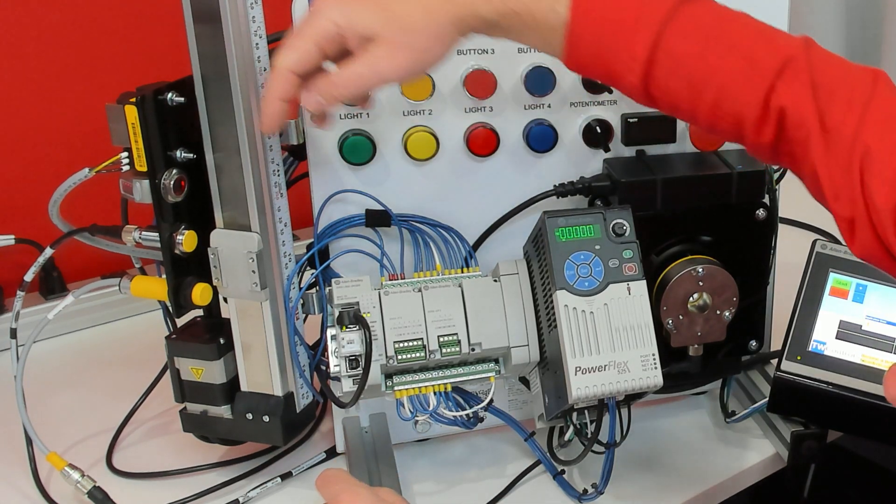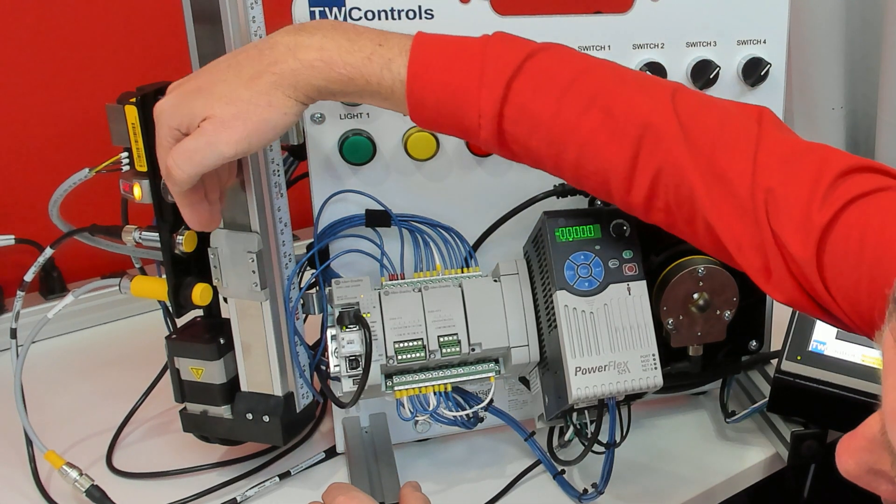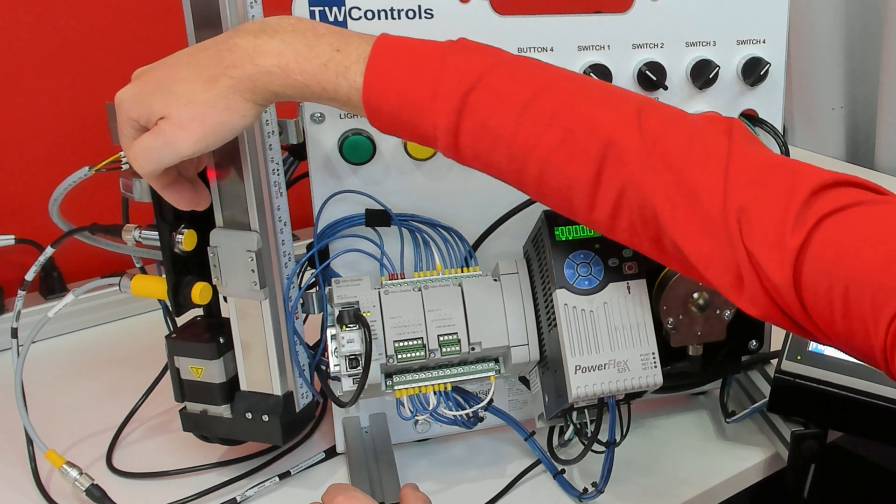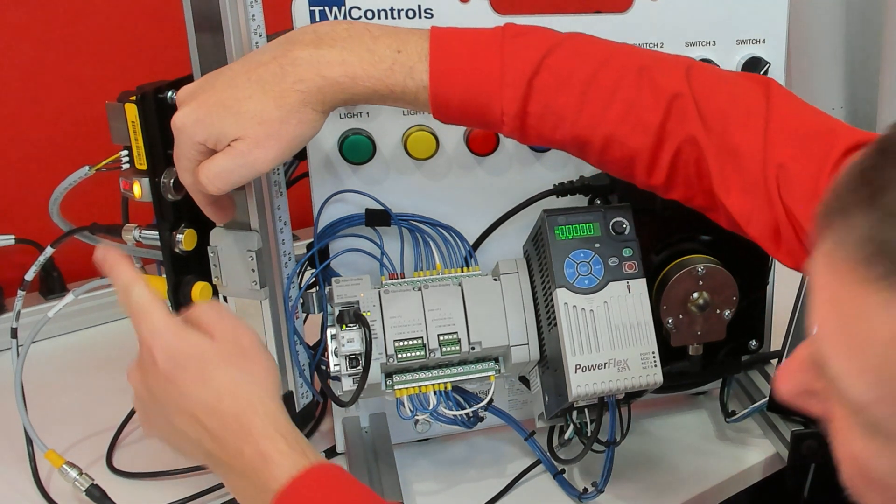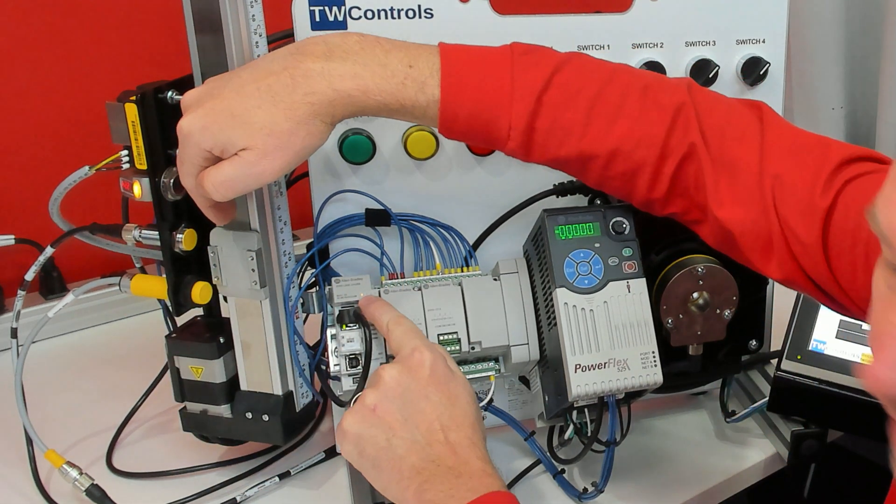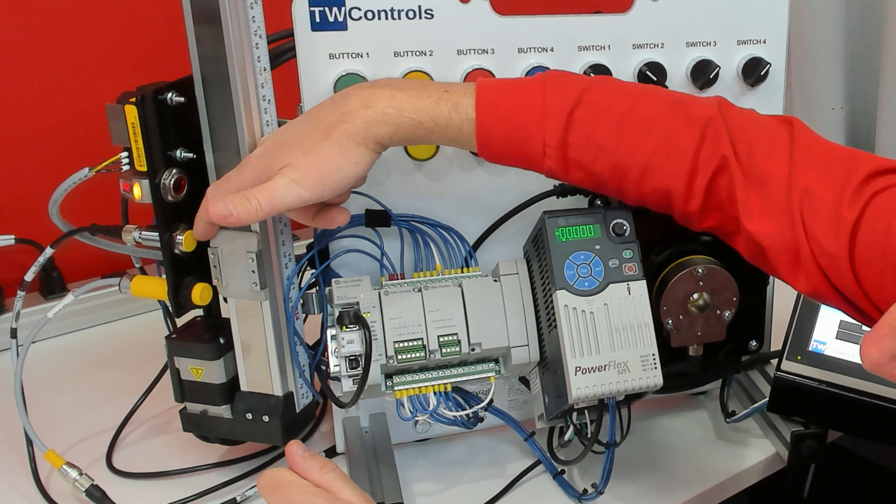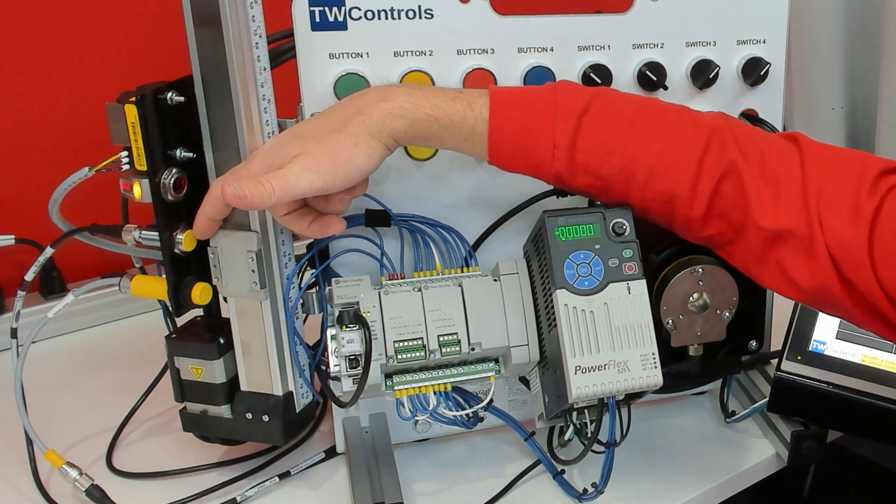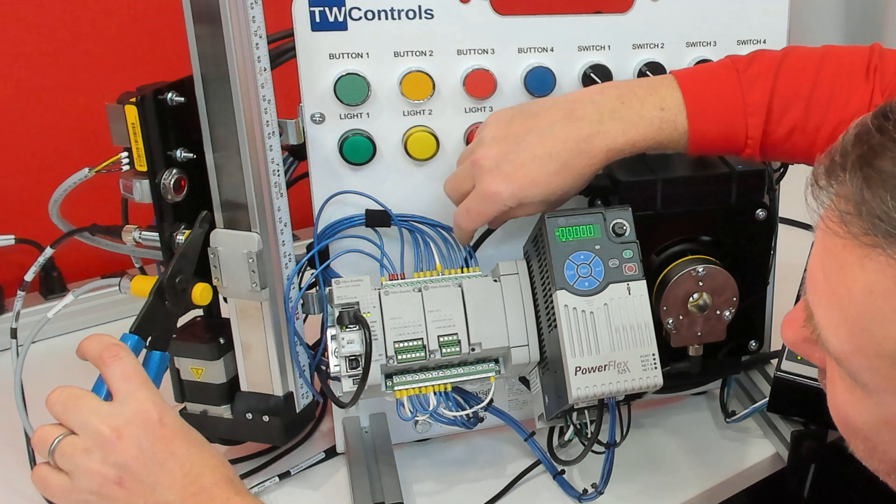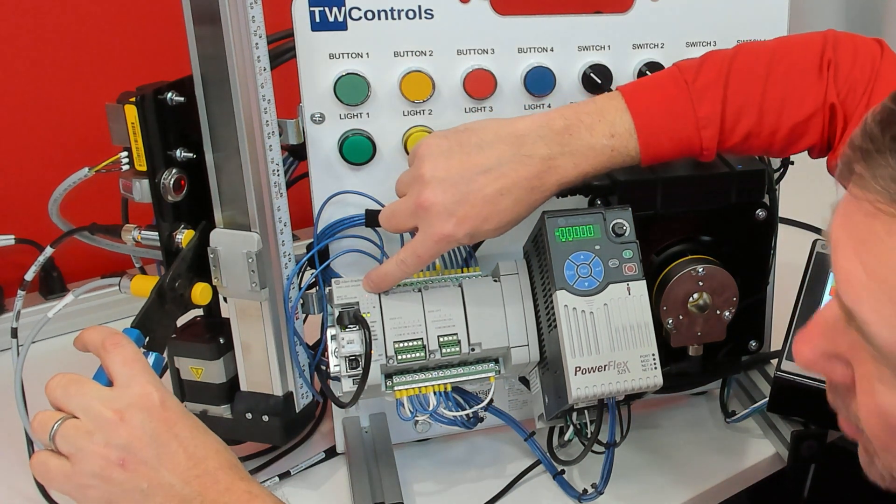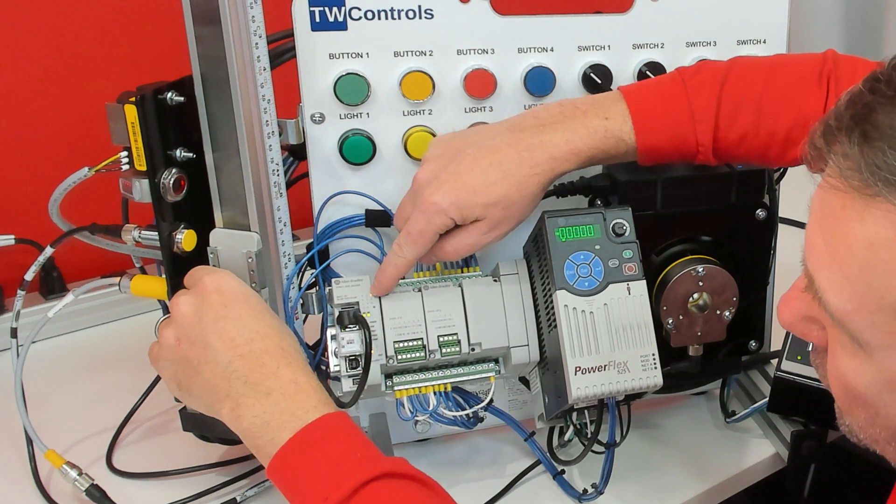And now, if we put our hand over the laser, now be careful, if you put it too close, notice the switch is off, if we put our hand so that it is illuminated here, we are now getting input zero here. Now we have an inductive prox here, so we can't flag that one with our hand. So if we take a piece of metal that I bring, we are getting input one, and then we can use our hand on the capacitive prox, and we stick our hand over it, we're getting input two.